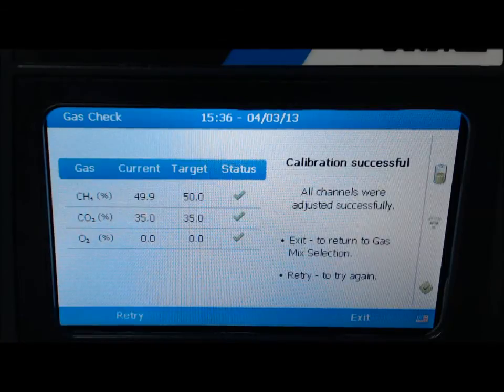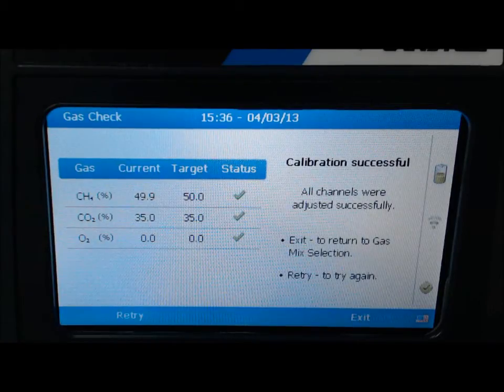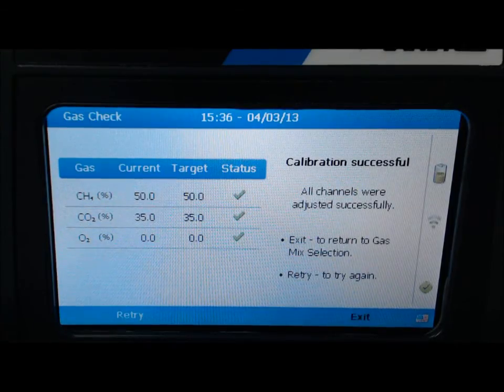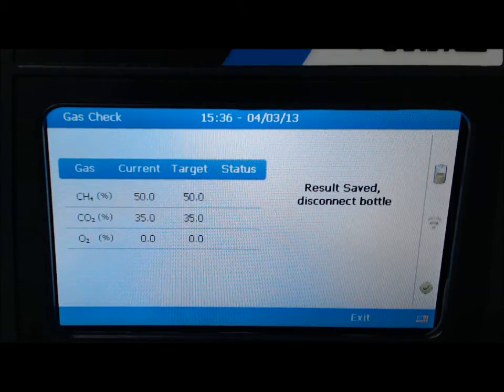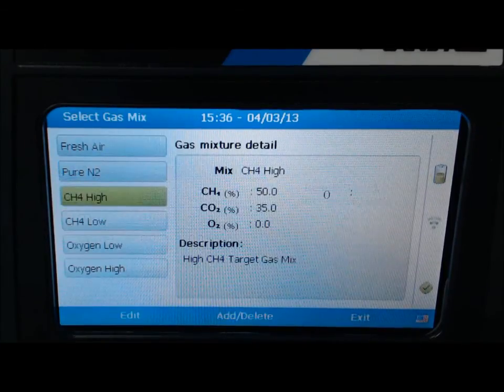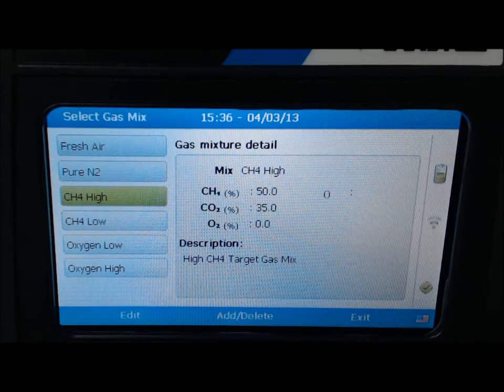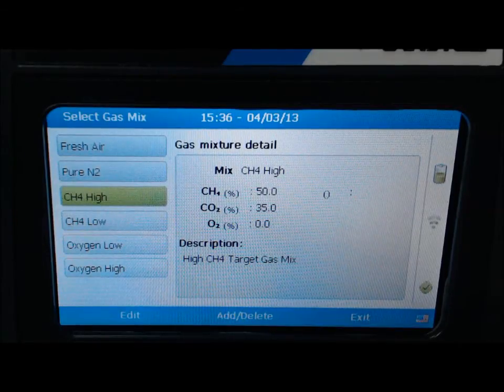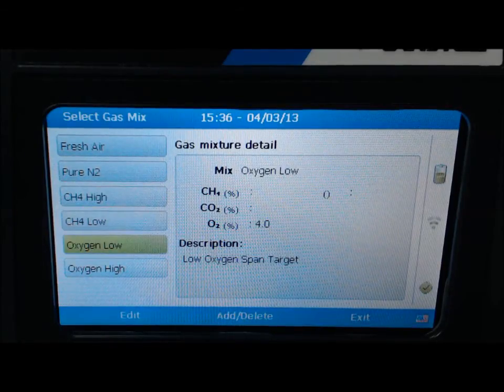At this point, you will need to turn off your pressure regulator, disconnect the hose, then select exit to save the results. Select exit once again to continue. This will take you to the gas mix screen. Select gas mixture oxygen low using the arrow keys to span O2, then press enter.